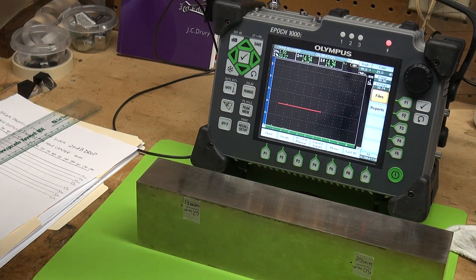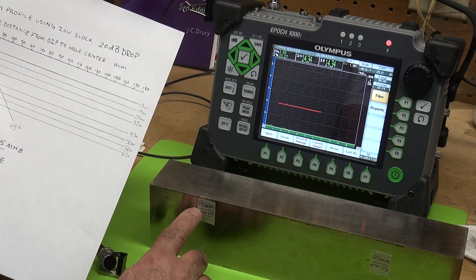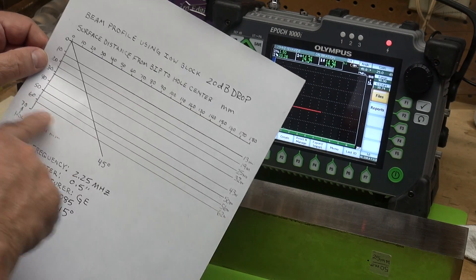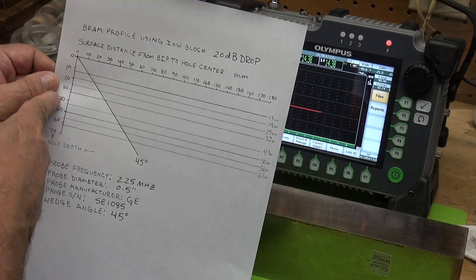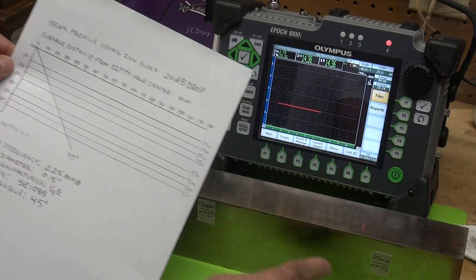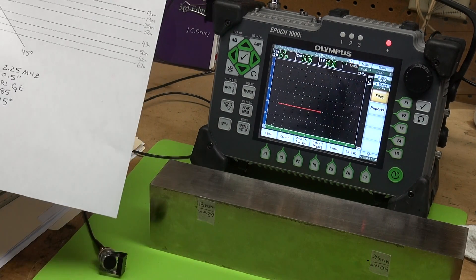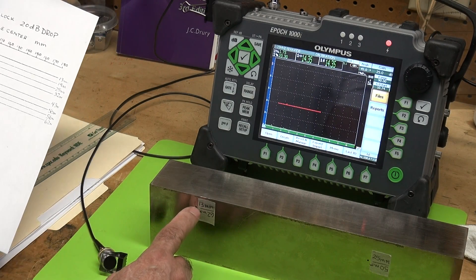I'm going to give you a quick demonstration of how to plot your beam spread. I'm using a two and a quarter megahertz transducer and a 45-degree wedge. The way we plot this beam spread is I'll aim the 45-degree transducer at the 13 millimeter hole. On this chart, the depths of the holes — 13, 19, 25, 32, all the way down to 62 millimeters — are on one axis, and the surface distance from the beam index point to the center of the hole is on the other axis.